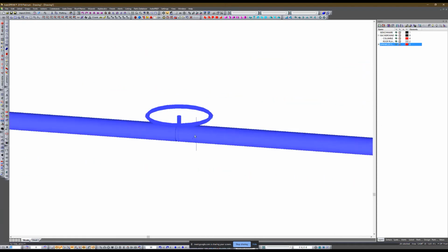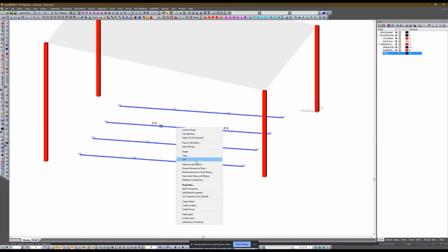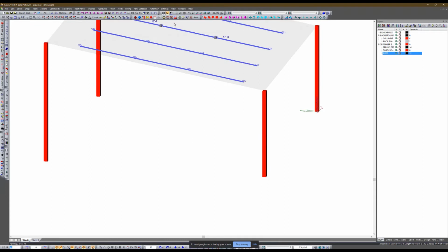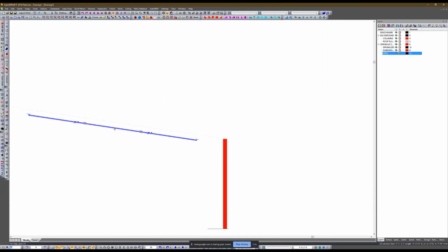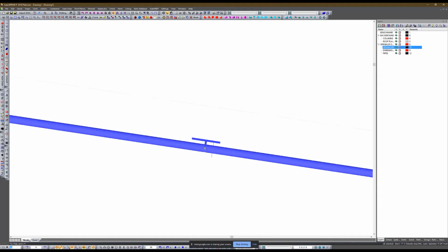Again, nothing's cut in here, pipe is broken at the sprinklers, but if I elevate all of these things to the roof plane, currently everything is at the same elevation. Sprinkler head location and center of pipe location are all a typical distance directly below, in a truly vertical distance from this roof plane, not a perpendicular distance.